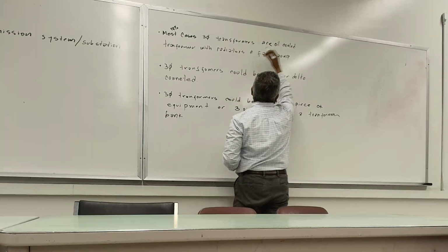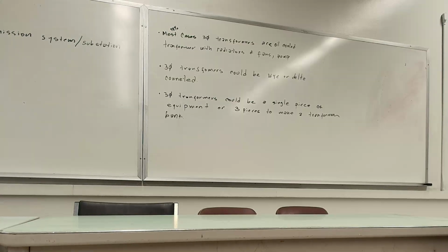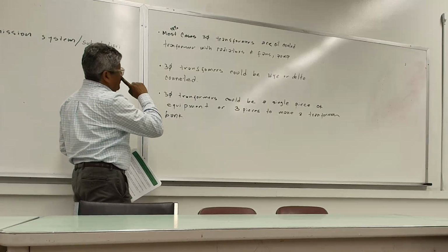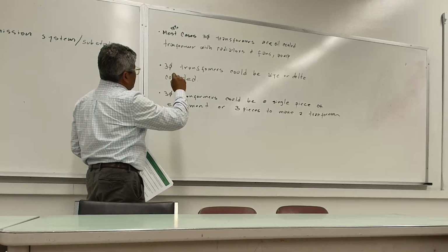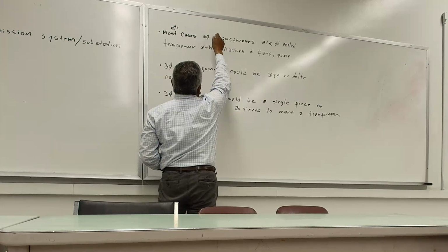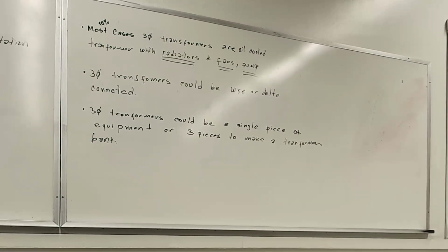So you can use radiators with fans and a pump to increase the capacity. And that has to do with the materials, right, of the core especially, because that's where you incur most of the losses, the type of windings. As a matter of fact, we were discussing this last week with a transformer manufacturer, an Edison, and this company now says we can get very high transformation, MVA-wise, without the need for radiators, fans, or pumps, which obviously is their trademark.